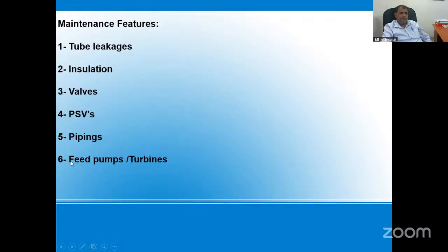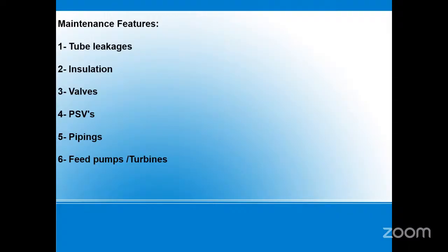Piping, I explained. Feed pump: our feed pump is an 11 stage centrifugal pump. Periodic maintenance is needed to avoid any failure during the running condition. All the engineers ensure its reliable and sustainable operation by changing its oil, by changing its bearings so it won't get damaged, and other things.